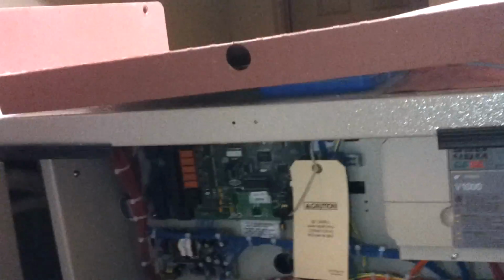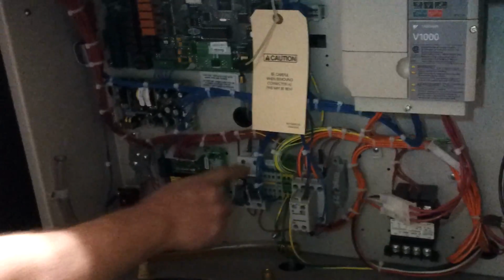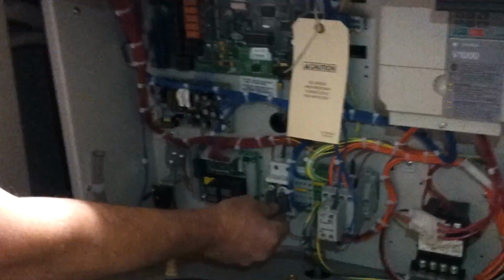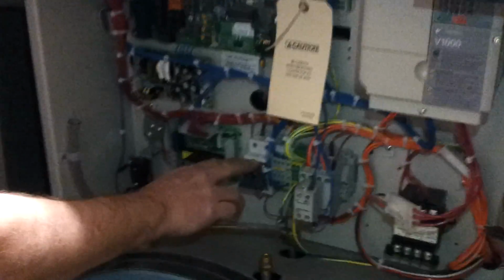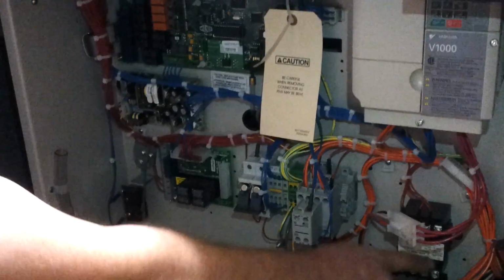Now generally if you have an issue, I'm just going to turn this off for a second. These are your two barrel fuses right here. And generally if one of these blows, you generally have a problem with the transformer, the inverter, or the motor.